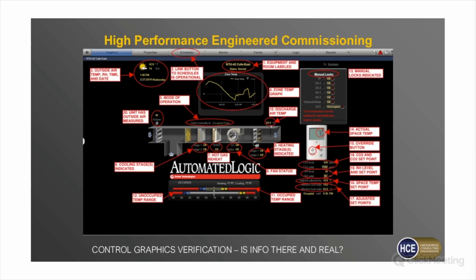And one of the things that's important is, as we tighten schedules, as we tighten set points, we put limits on, we're only allowed to cool to 74 and we're only allowed to heat to 70. As we do that, if our sensors are not accurate, then the occupants become uncomfortable, and we'll find ways to get around that. You've got to check, are all your stages working in all your cooling? Are all your heating stages working? All these different items. Is this information that your energy managers and your controls people are making decisions about how to run the building accurate?